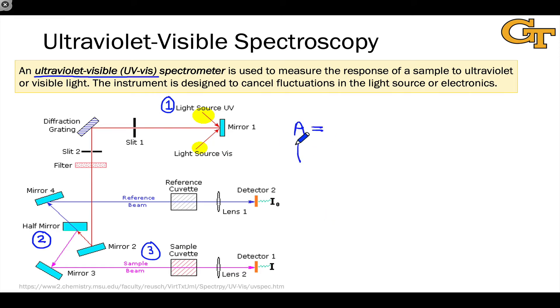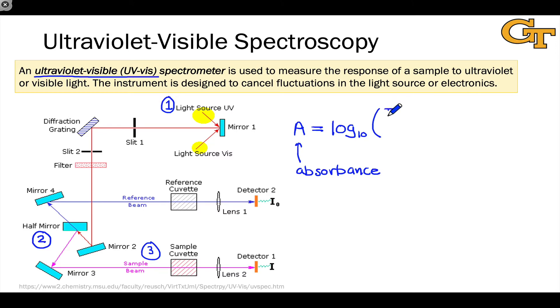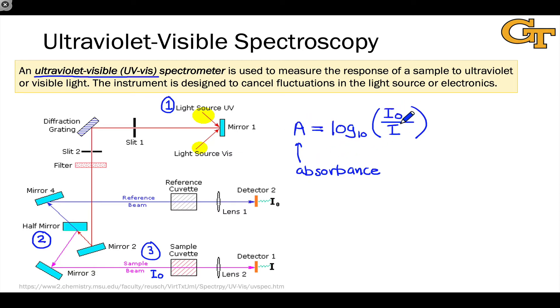What we call the absorbance, A, is a measurement of the amount of light absorbed by the sample. For colored samples, the extent of light absorbed can be quite large, so absorbance uses a log value to account for this. It's the log of the incident intensity I0 divided by the intensity of light transmitted, measured by detector one. Placing I0 in the numerator ensures that absorbance is a positive value when light is absorbed, since I0 over I will be greater than one when light is absorbed.